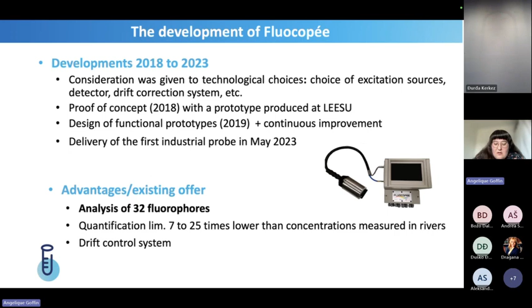After having various proofs of concept and prototypes we made at LEESU, we finally arrived at a functional prototype, and it was subject to various continuous improvements. And since May 2023, we now have a first industrial probe available. The advantage of the sensor is that it is now able to analyze 32 excitation emission wavelengths, which is much better than only the 2 or 3 excitation emission wavelengths usually used in other sensors. We are able to have a good quantification limit, 7 to 25 times lower than the concentration measured in rivers, which means we can use this sensor in various environments. We also improved the drift control system, which is not commonly used in fluorescence sensors currently.